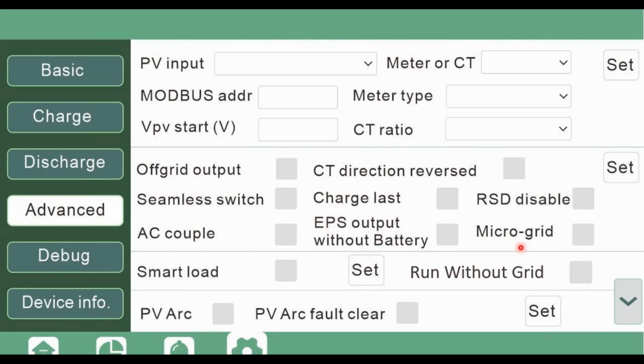Your battery is drained. Maybe you're using lead acid batteries. You don't need to do anything other than enable EPS output without battery, and it will charge your batteries. Here you would enable the smart load, and then if you were running the system off grid, you would just enable the run without grid feature here.